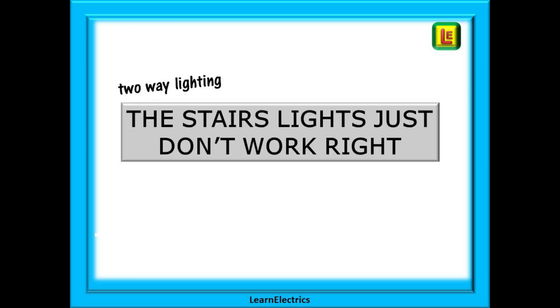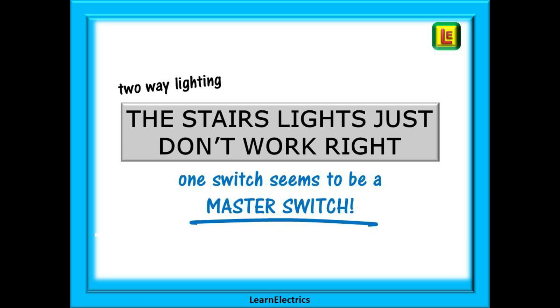A frequent problem with two-way lighting is found when the customer complains that the stair lights just don't seem to work right. And this also fools some electricians if they've not seen this before. I've had more than one customer tell me that it seems like one of the switches is a master switch. If we turn the light on from the bottom of the stairs it is possible to turn it off from upstairs. But if we turn the light on at the top of the stairs then we cannot turn it off at the bottom switch. We have to turn it off again at the top and then the bottom will work again.